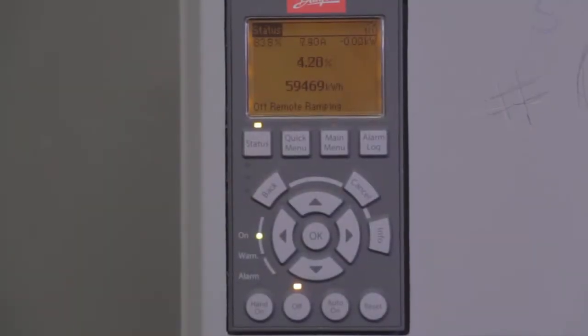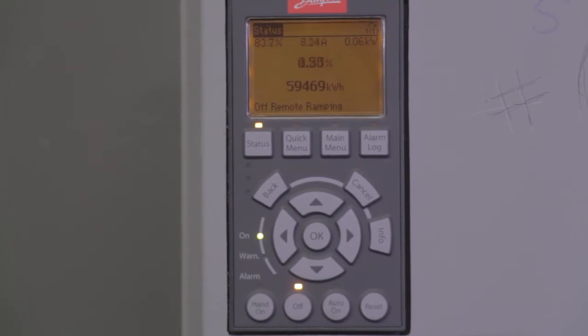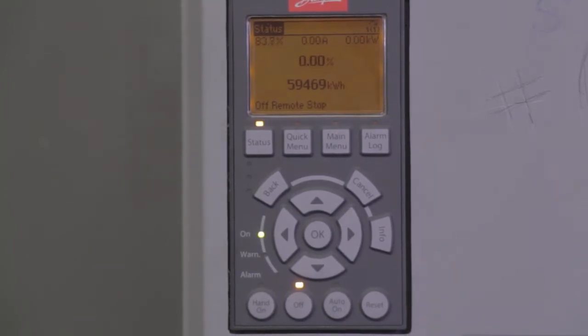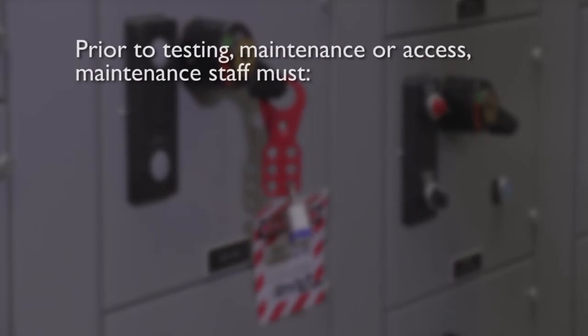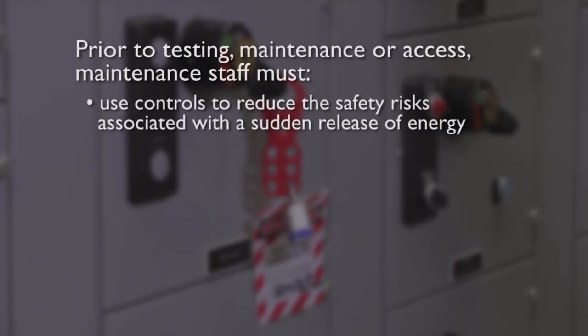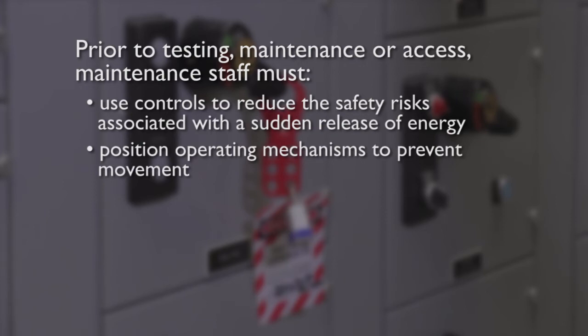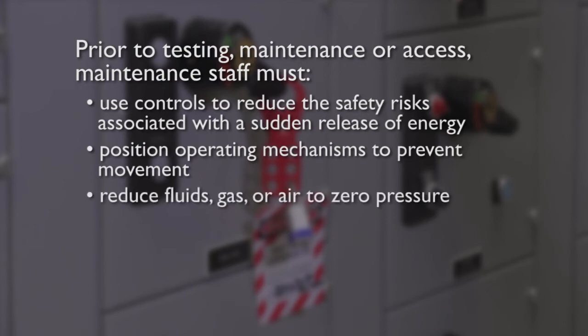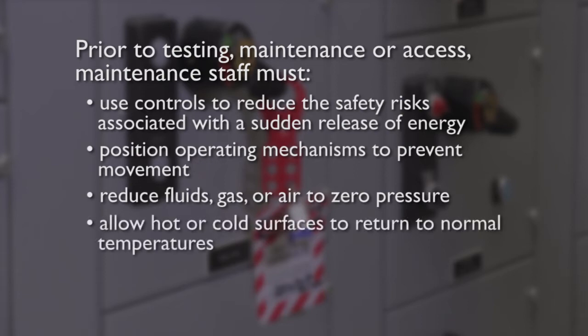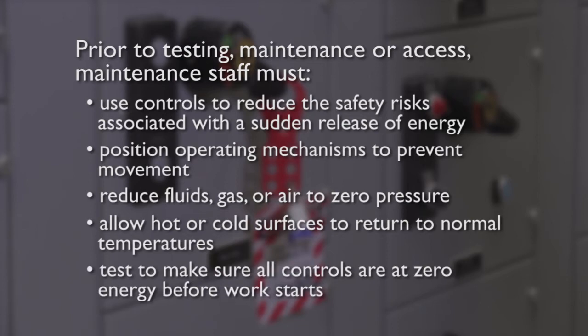Always double check that the lockout equipment is secure and the energy source is at 0. Prior to testing, maintenance, or access, maintenance staff must use controls to reduce the safety risks associated with the sudden release of energy, position operating mechanisms to prevent movement, reduce fluids, gas, and/or air to 0 pressure, allow hot or cold surfaces to return to normal temperatures, and test to make sure all controls are at zero energy before work starts.